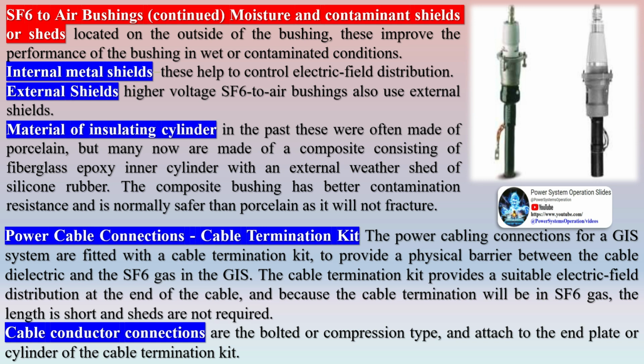Material of insulating cylinder: in the past these were often made of porcelain, but many now are made of a composite consisting of fiberglass epoxy inner cylinder with an external weather shed of silicone rubber. The composite bushing has better contamination resistance and is normally safer than porcelain as it will not fracture.